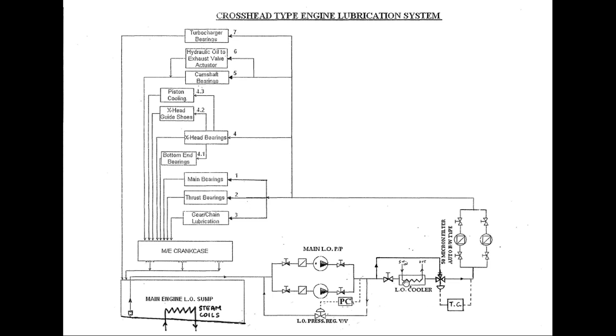From the pump discharge, lube oil goes to the lube oil cooler, which may be sea water or fresh water cooled. The pressure on the lube oil side is always kept higher than the cooling water pressure to avoid contamination of lube oil in case tube leakage occurs — we don't want sea water mixing with lube oil as that would corrode the engine. A temperature control valve is provided which automatically controls the temperature of the lube oil outlet.